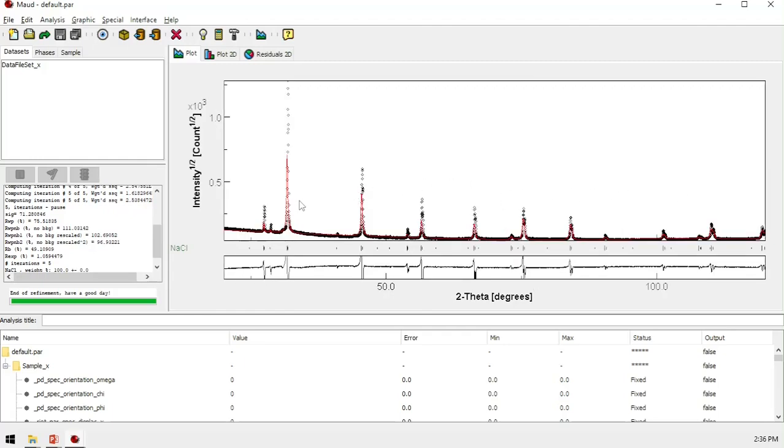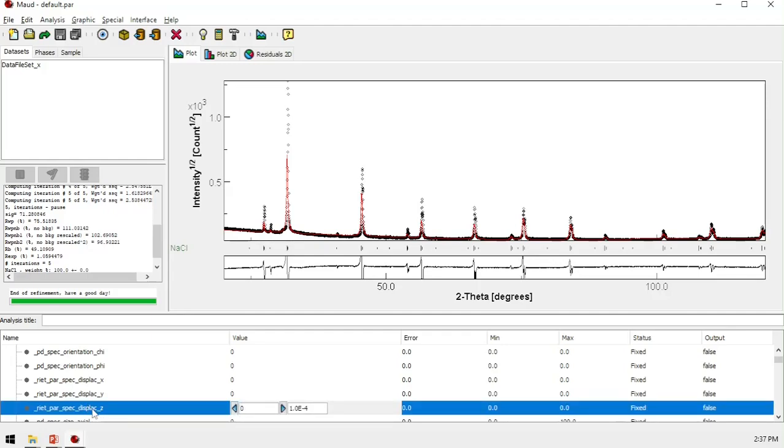One of the possibilities in this measurement is that the sample is not at the correct height when it's prepared. To refine and correct it, we will compensate the position of the diffraction pattern.